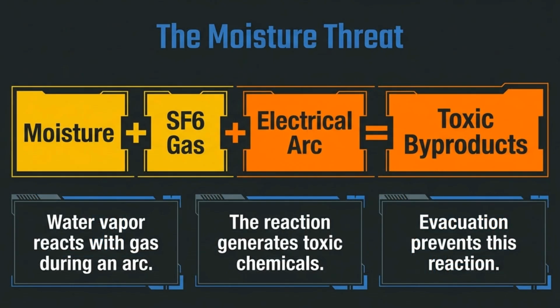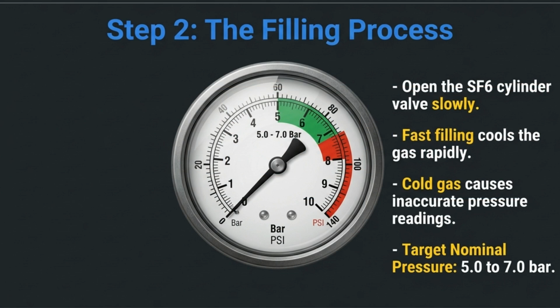The moisture threat is serious. Water vapor reacts with SF6 during an arc, generating toxic chemicals. Proper evacuation prevents this dangerous reaction. Step 2 is the filling process. Open the SF6 cylinder valve slowly. Fast filling cools the gas, causing inaccurate pressure readings. Target a nominal pressure between 5.0 and 7.0 bars.